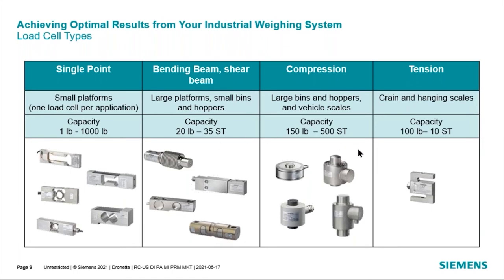Compression cells are the real heavy-duty cells, with maximum capacities ranging from 150 pounds up to about 500 tons. They can be used on very large bins — with a four-legged bin you could get up to 2,000 tons in a weighing system. Compression load cells would also typically be found in vehicle scales, such as truck scales. Tension load cells are designed for cranes or hanging scales. The S-type cell shown here is named for obvious reasons, and tension cells range in capacity from 100 pounds up to about 10 tons.